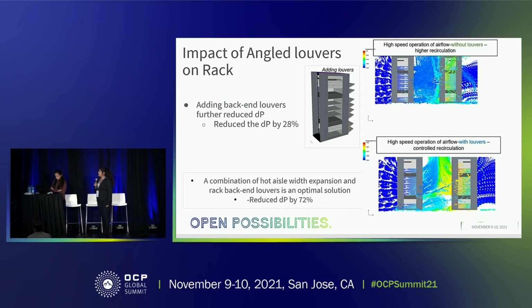The other aspect is including the angle louvers on high power racks. As I discussed earlier, just to refresh your memory, this is the type of behavior that we would see if there is a high power rack rear facing a low power rack. So now when we include angle louvers, as expected, the air is now being deflected towards the ceiling, and the simulation has shown that there would be a reduction of 28% in aisle differential pressure. We have run an additional analysis where we expanded the hot aisle width by 1 foot and also included the angle louvers. In that case, we saw a reduction of differential pressure by 72%, basically similar pressure ranges to what we would see in a baseline case.